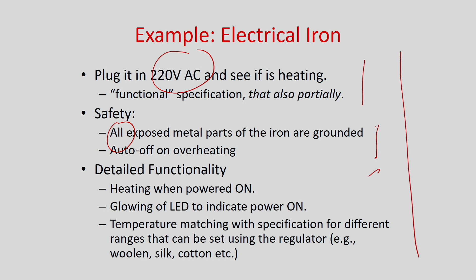But if it is a more expensive one, you have to check that all exposed parts are grounded and that auto overheating off works. We can even go for more detailed testing, like heat when the power is on, glow of the LED, then temperature matching with specification, like wool, silk, cotton, etc. So the more sophisticated a device becomes, the more sophisticated the testing becomes. But still, this technology was known more than 50 years ago, and it remains more or less the same. So the yield is very, very high. So testing is not that important in such cases, because if I make 10,000 irons, maybe only one or two will have a defect, and it can be very easily verified by the shopkeeper.